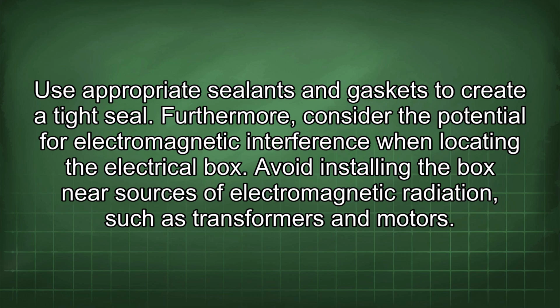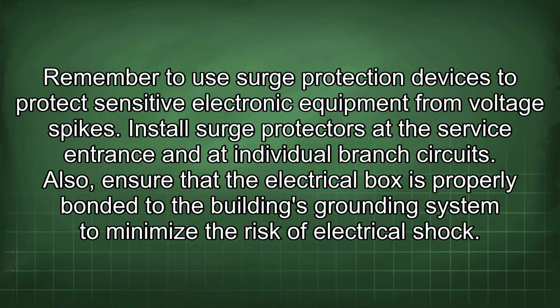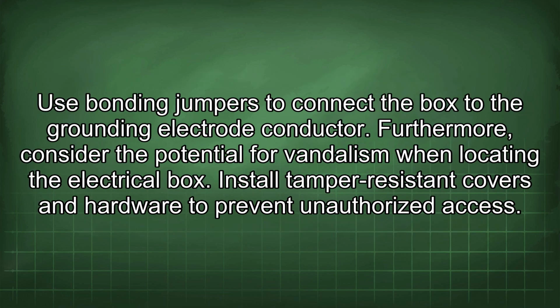Furthermore, consider the potential for electromagnetic interference when locating the electrical box. Avoid installing the box near sources of electromagnetic radiation, such as transformers and motors. Remember to use surge protection devices to protect sensitive electronic equipment from voltage spikes. Install surge protectors at the service entrance and at individual branch circuits. Also, ensure that the electrical box is properly bonded to the building's grounding system to minimize the risk of electrical shock. Use bonding jumpers to connect the box to the grounding electrode conductor.